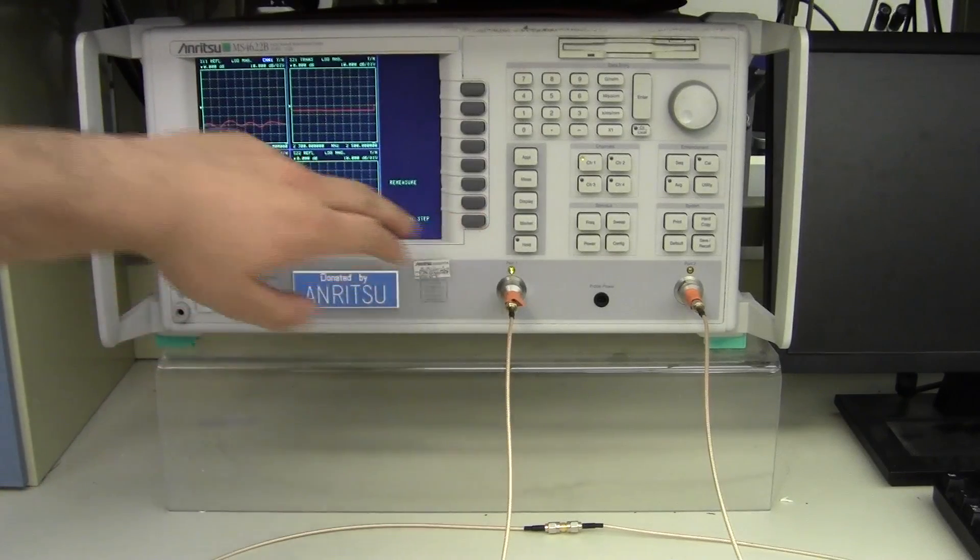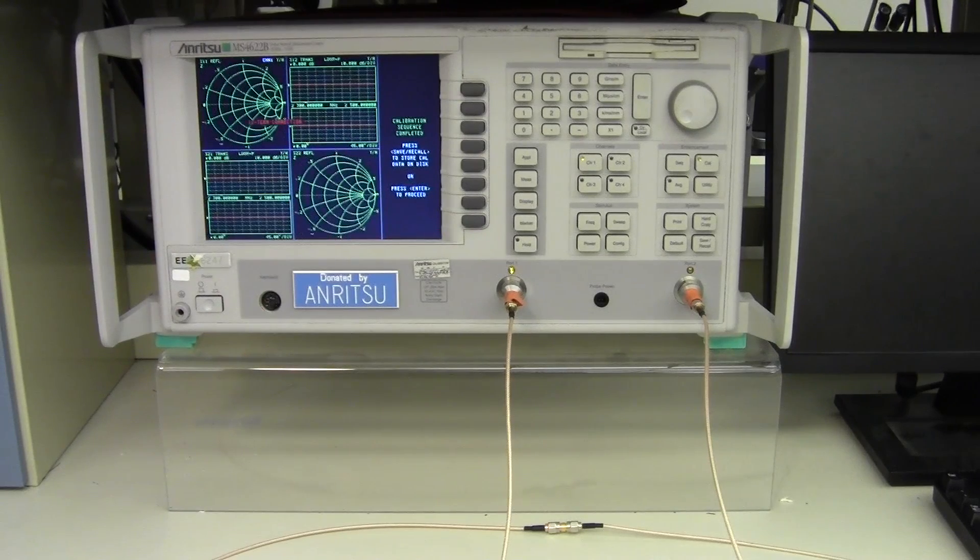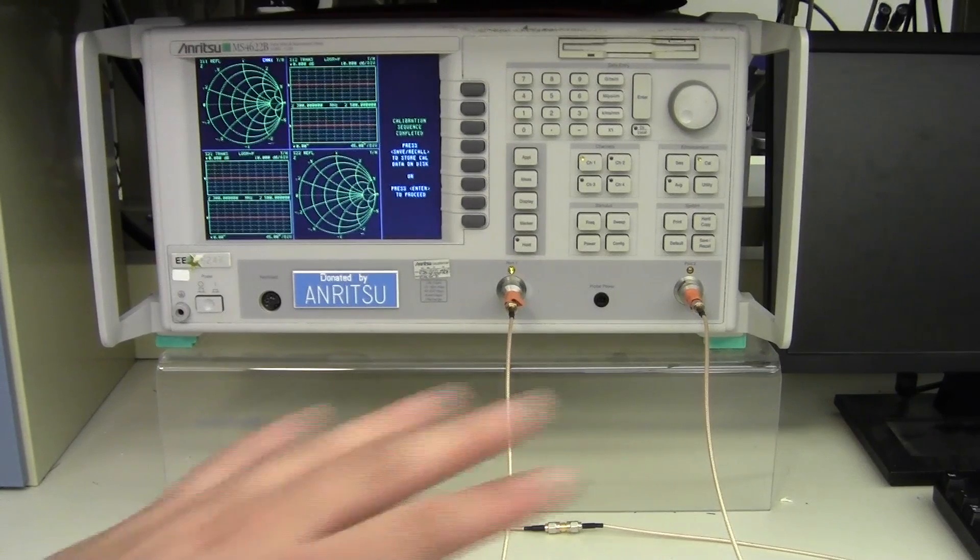Measurement completed. Next calibration step. And it says calibration sequence complete. Press save recall to store calibration or press enter to proceed. Since these calibration readings are only valid for these specific pieces of coax in this specific configuration, there isn't much point in saving your calibration. And so we'll just move on.